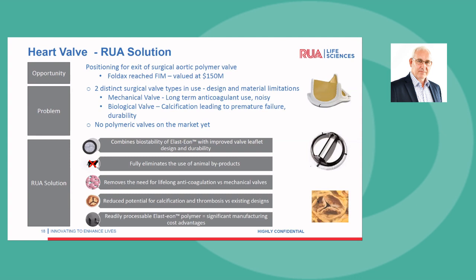One is the benefits of an Elast-Eon material. It is the most biostable of long-term implantable polyurethanes, and doesn't have the problems of other materials. In addition, we've got what we think is an exceptionally good design that has limited the level of stresses on the heart valve leaflets. We've fully eliminated the use of animal byproducts by having a valve that's more like the natural valve.